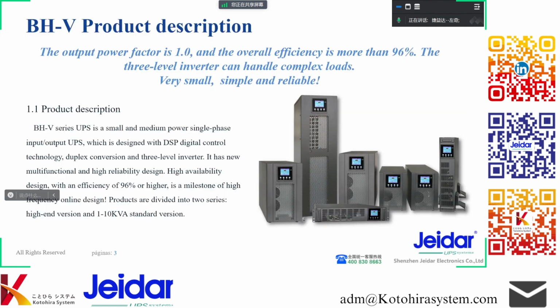The output power factor is 1, and the overall efficiency is more than 96%. The three-level inverter can handle complex loads, very small, simple, and reliable. BH-V series UPS is a small and medium power single-phase input or output UPS, which is designed with DSP digital control technology, duplex conversion, and three-level inverter. It has a new multifunctional and high reliability design.